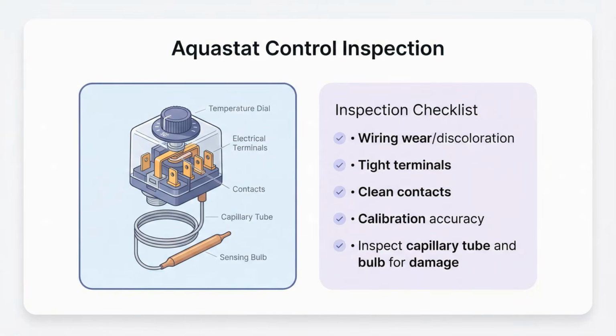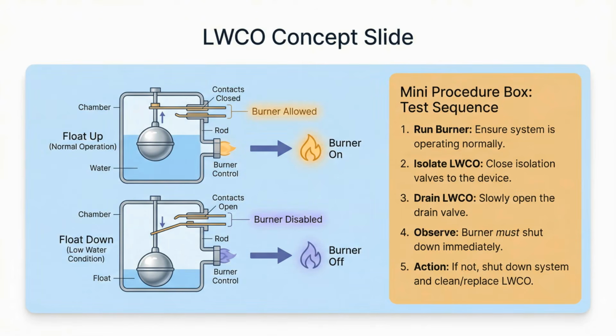Limiting controls like aquastats are maintained much like thermostats. Inspect wiring and terminals, clean contacts, and verify calibration. Also inspect the capillary tube and sensing bulb, because damage there can cause incorrect temperature control or a failure to respond. A float-type low-water cutoff protects the boiler from firing when water level is too low. If contaminated water causes the float to seize closed, the boiler could keep firing during a low-water condition, risking serious damage. The test is straightforward. With the burner running, isolate and drain the LWCO so the float drops. The main burner should shut down. If it doesn't, shut the system down and clean or replace the LWCO.